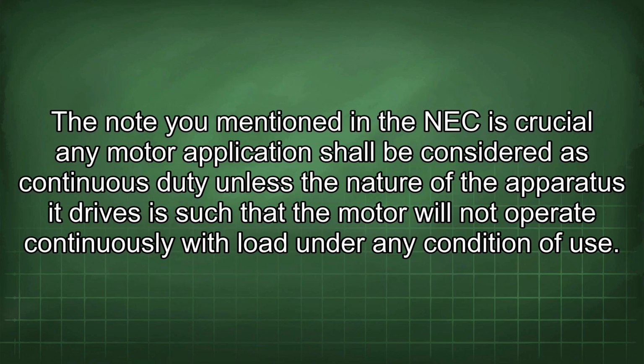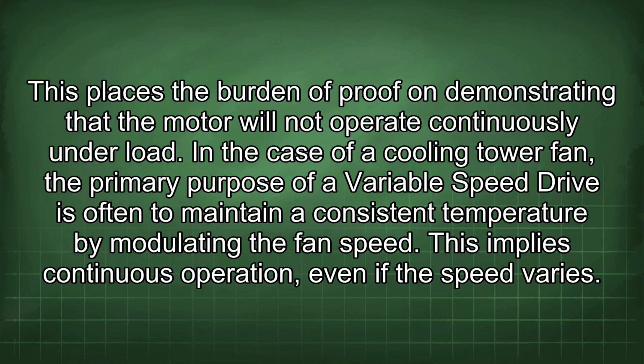The note you mentioned in the NEC is crucial. Any motor application shall be considered as continuous duty unless the nature of the apparatus it drives is such that the motor will not operate continuously with load under any condition of use. This places the burden of proof on demonstrating that the motor will not operate continuously under load.